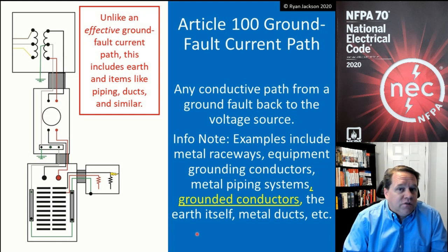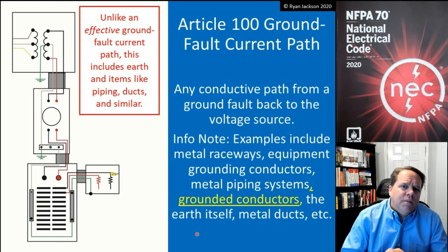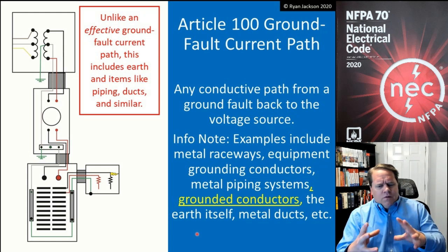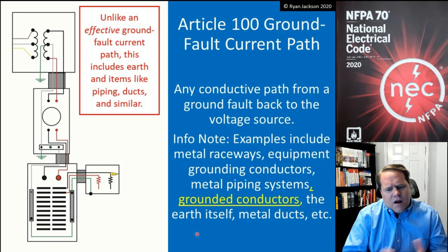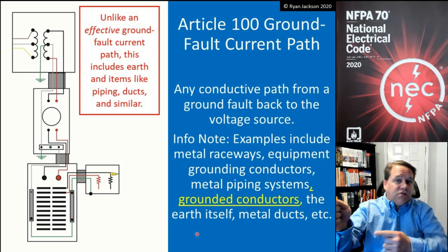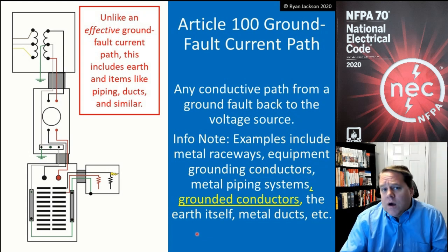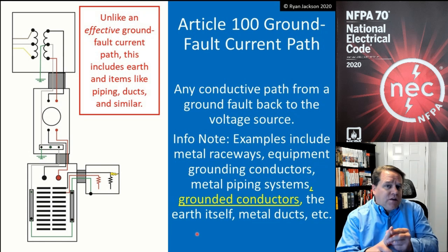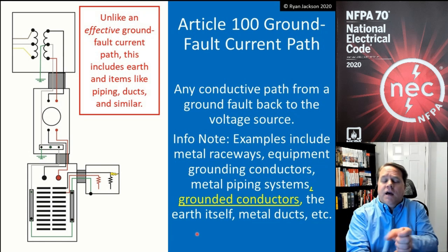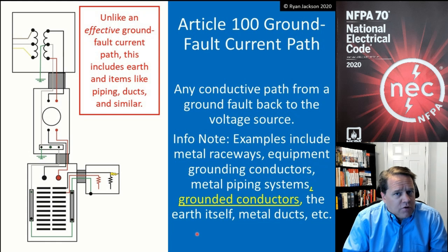It will carry current back to the source, but our contact resistance of an electrode to the earth is so high that it wouldn't initiate an overcurrent device. If you think about it, there's that magic number people talk about, 25 ohms, when they talk about ground rods. What is that really a measurement of? Is that a measurement of the resistance of planet Earth? Well, obviously not, because it varies from installation to installation. What are we really measuring when we measure the impedance of a ground rod? Well, we're measuring the contact surface between the rod and the dirt surrounding it.